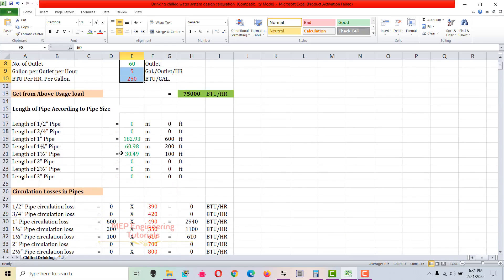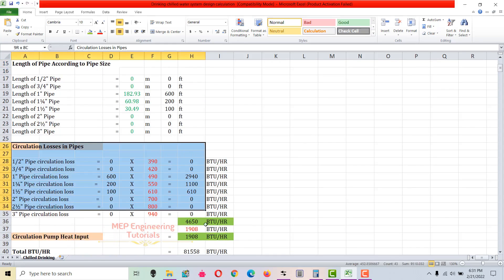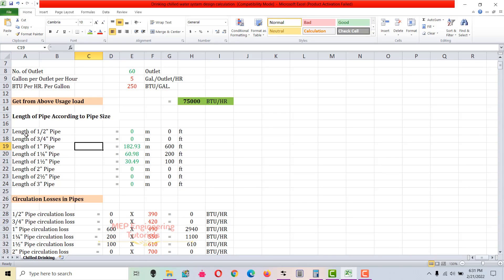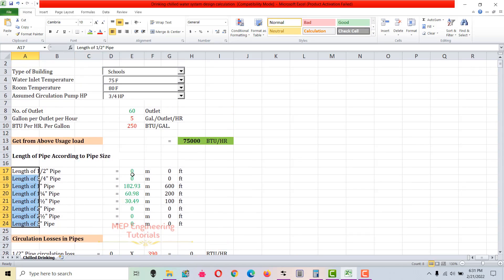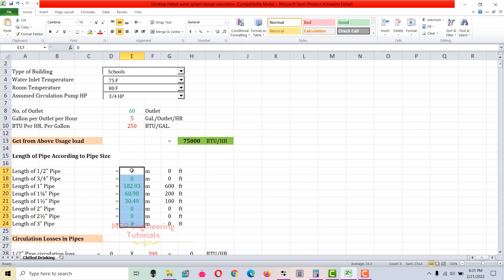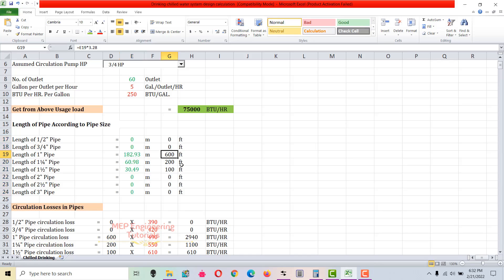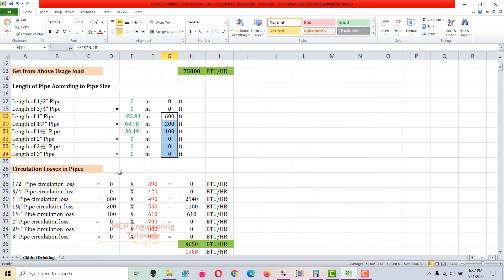Next we calculate circulation losses in the pipes, but before that we have to enter all the piping lengths used in the project. You have to go to the drawing, check the length of each pipe segment, and add it here. After checking the lengths for each pipe segment from the drawing, I've entered them here. We need to convert these to feet, so multiply the value by 3.28.